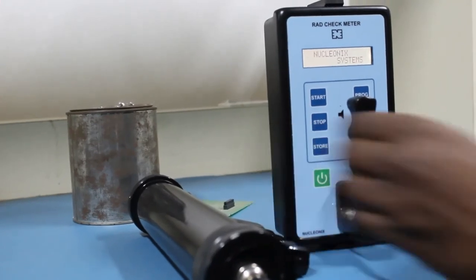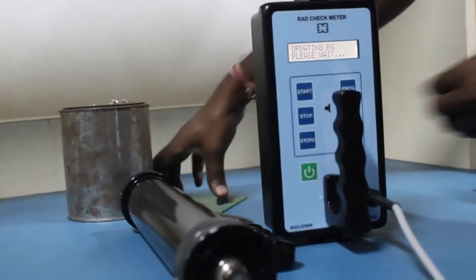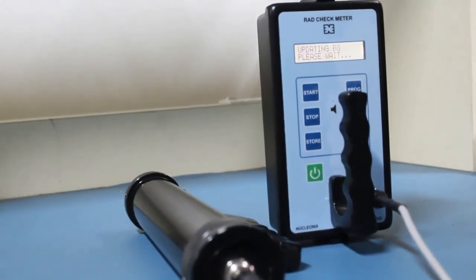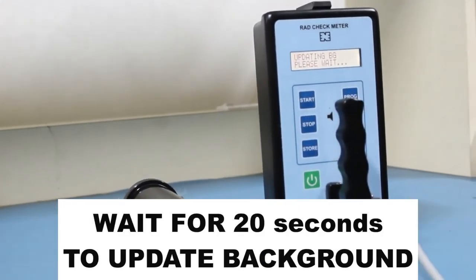For measuring the natural background, please ensure to keep the detector 1 meter from the ground and 4-5 meters away from the scrap for about 20 seconds. Then the background appears.